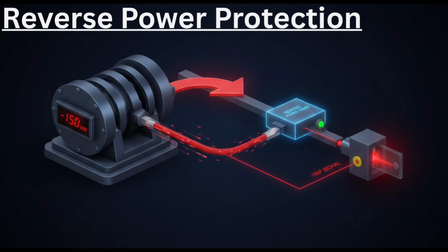Reverse power relay detects negative power flow direction. If reverse power exceeds preset limit, the breaker trips automatically. This prevents engine damage and protects the shaft system. Reverse power relay is especially important in load sharing situations. Engineers must always monitor power meters during parallel operation.